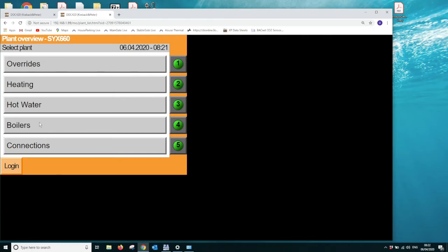Each of these bars are elements that you can click on to go into, and all we do is we select, first of all, the functionality of the controller. We're going to set up how we want this controller to work. So I'm going to assume that we've got a typical optimizer compensator circuit where we've got 2 boilers, a variable temperature circuit, and we've got some hot water that I need to have boiler linked to the controller. So we want to have the boiler to operate when there is a demand for hot water.